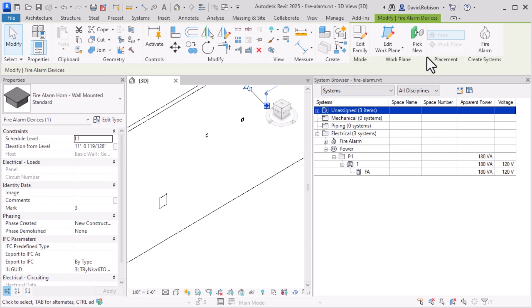I've got a couple of fire alarm devices here. We can connect the first one, you can see it connects. We can connect the second one. And when we connect this third one, we get a warning message saying we've exceeded the number of circuits. It's similar to the max number of single pole breakers on power panels, just the same feature applied to other panels.